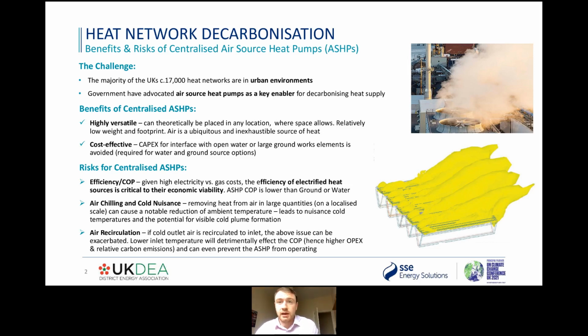The efficiency, the COP, has to be as high as possible as a result of the high electricity tariffs, or electricity costs versus gas costs, and that means that the efficiency of our heat supply needs to be as high as possible to ensure the economic viability. Particularly the issues that we're investigating today relate to the efficiency, but are more centred around this air chilling and cold nuisance issue.